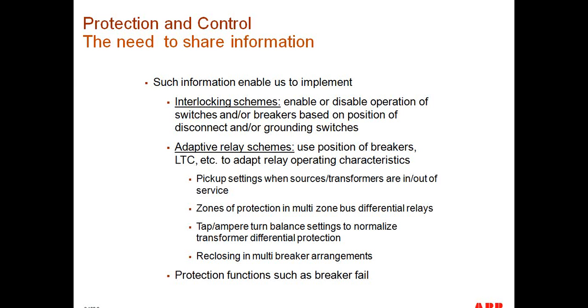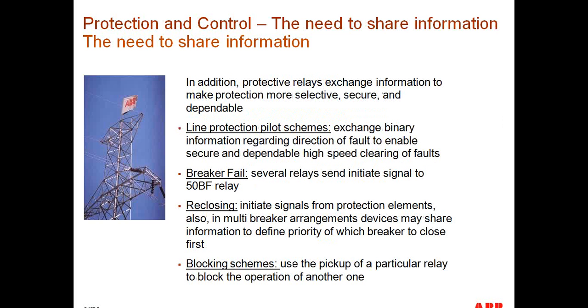Another reason where information needs to be exchanged between relays could be in multi-breaker reclosing arrangements, where devices need to choose, based on pre-fault conditions, which breaker is going to energize the line and which one is not. In most cases, if both breakers are closed and a trip occurs, there's always a predefined breaker that's the one that's going to energize the line. But if either of those breakers is open, or out of service, then there needs to be some indication so that there are no further relays added to the reclosing or the re-energization of that line. All of these require information from other devices, and again, this information is exchanged via binary hardwired signals. Breaker fail, of course, is another one.